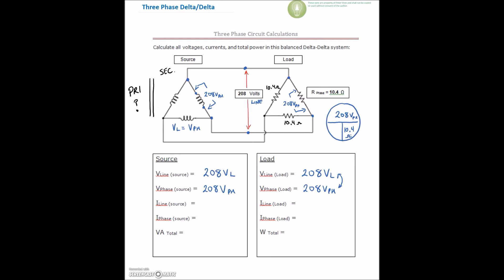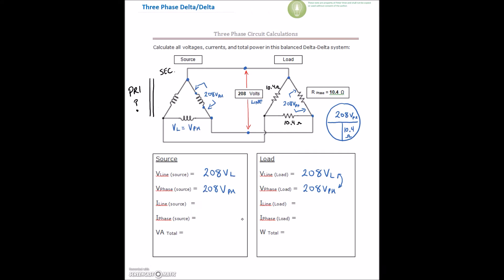So we've got 208 divided by 10.4. Let me just bring up the calculator here. You guys in my class always laugh when I say that math is not my strong point. Math is not my strong point. I can't do this in my head. So 208 divided by 10.4 gives me 20 amps.